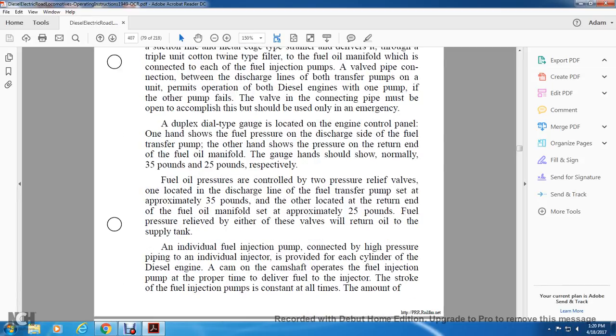A duplex dial type gauge is located on the engine control panel. One hand shows the fuel pressure at the discharge side of the fuel transfer pump. The other hand shows the pressure of the return end of the fuel oil manifold. The gauge hands should normally show 35 pounds and 25 pounds respectively. Fuel oil pressures are controlled by two pressure relief valves. One is located on the discharge of the fuel transfer pump, set at approximately 35 pounds. The other is located at the return end of the fuel oil manifold, set at approximately 25 pounds. Fuel pressure relief on either side will return the oil to the supply tank.